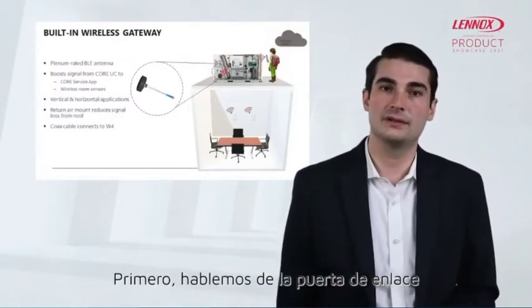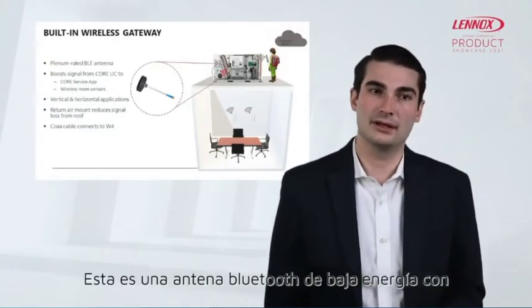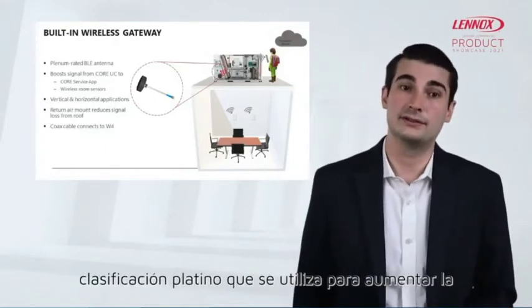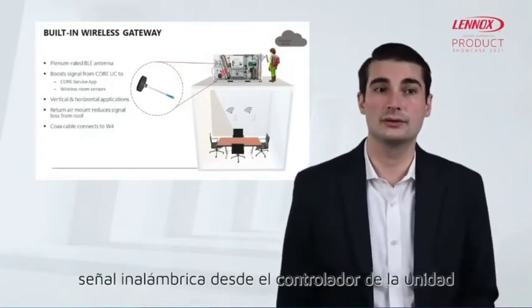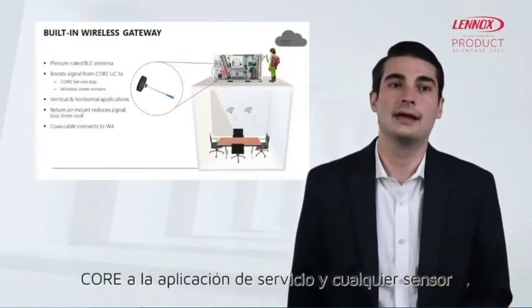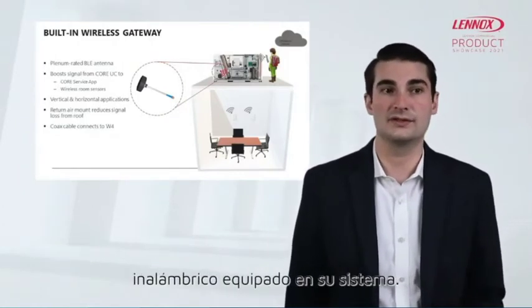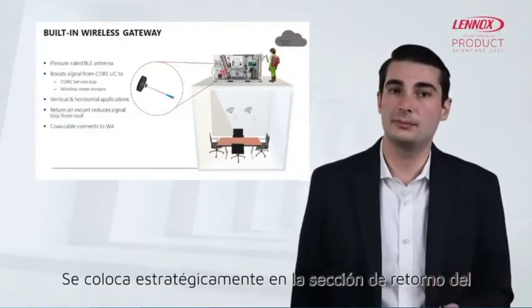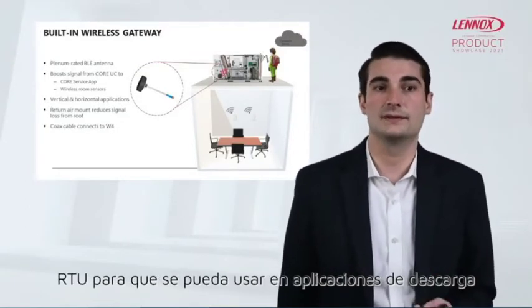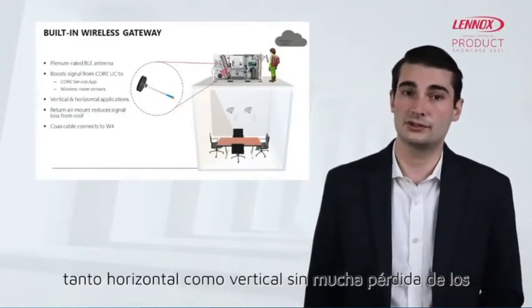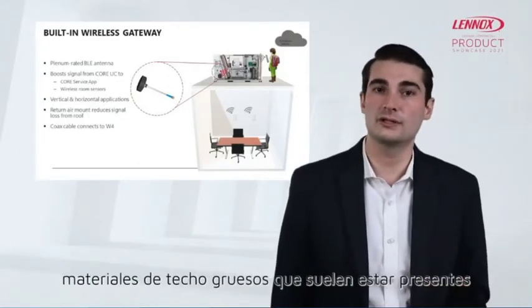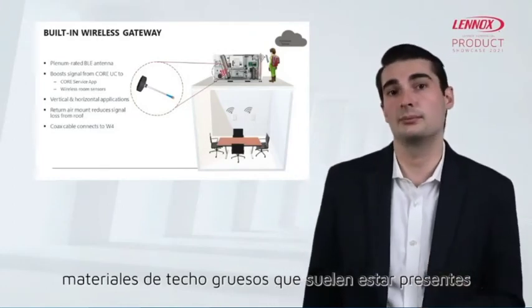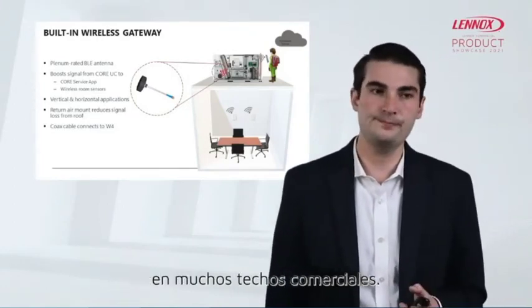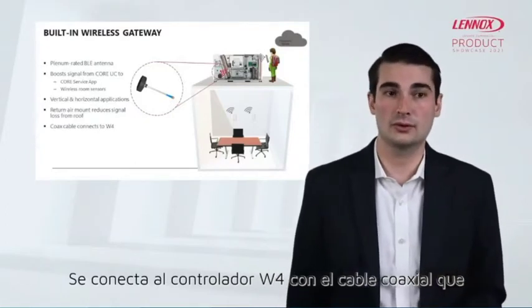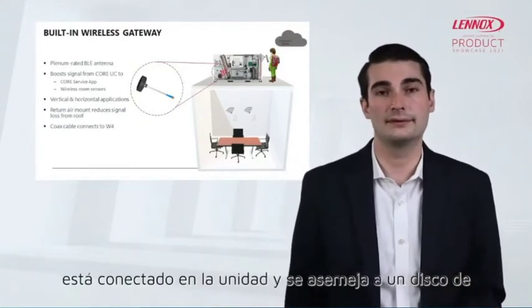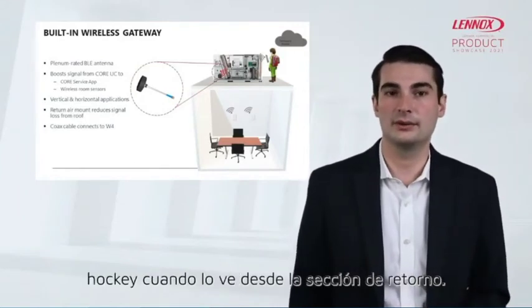First, let's talk about the built-in wireless gateway. This is a plenum-rated Bluetooth low-energy antenna that is used to boost the wireless signal from the core unit controller to both the service app and any equipped wireless sensors in your system. It is strategically placed in the return section of the RTU so that it can be used in both horizontal and vertical discharge applications without taking too much loss from the thick roofing materials that are typically present in many commercial roofs. It connects to the W4 controller with a coaxial cable that is wired in the RTU. It resembles a hockey puck when viewing it from the return section.